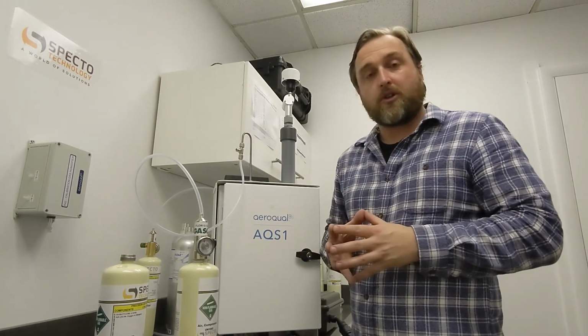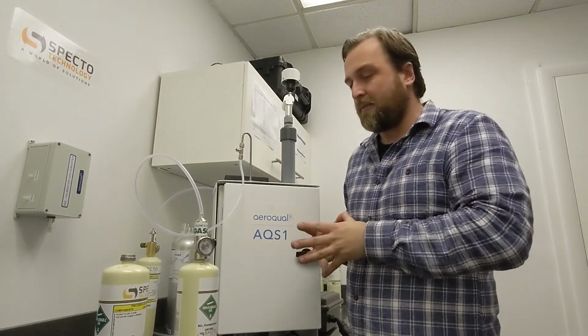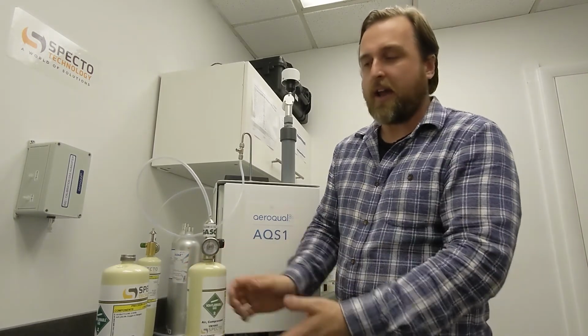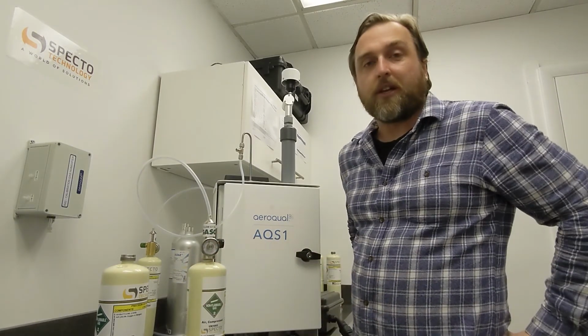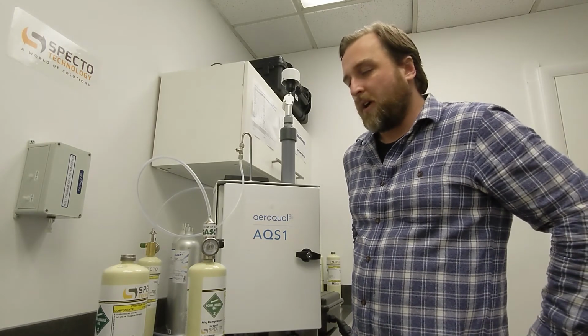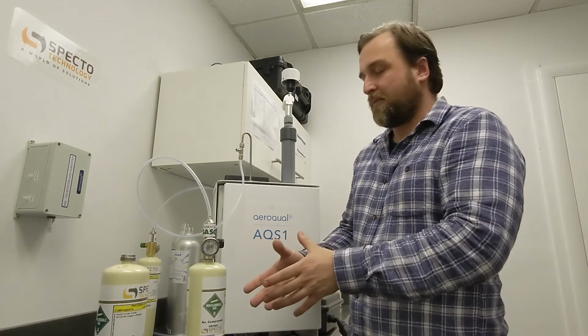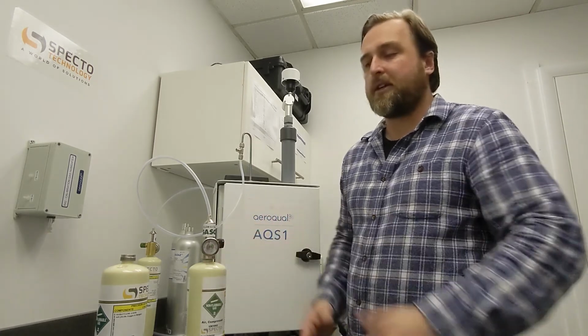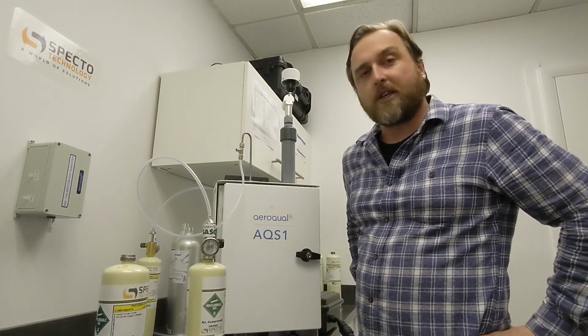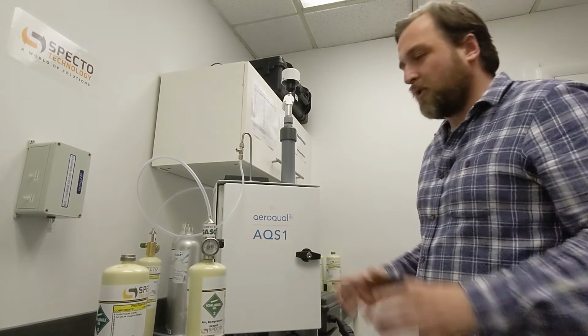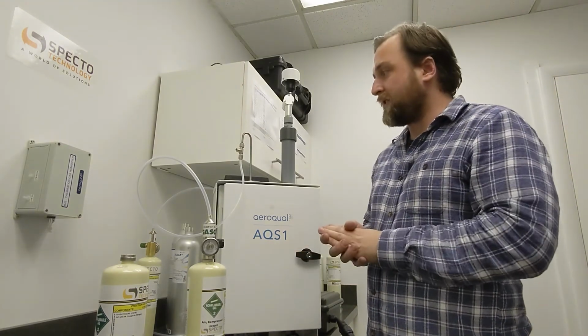There are two types of gases that we're going to provide for the calibration. There's zero air, and there is isobutylene, which is a VOC. So we're going to firstly calibrate at 0 and then calibrate with our VOC concentration. That is all there is to do from this side.